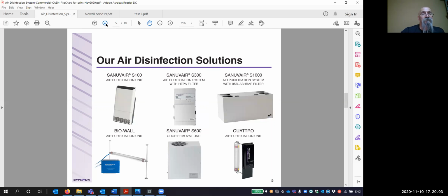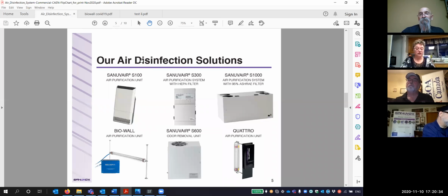Sure. Let's talk about air disinfection. Air disinfection is different than coil cleaning. It's all about time and intensity. With coil cleaning, the coil isn't moving. We have all the time in the world. You just have your UV right there at the coil, nothing's moving, and it's doing its job. With air disinfection, we have pathogens and stuff moving through the air very quickly. At a very low CFM, like 700 CFM, a pathogen or a spore will move over 5.5 feet in 1 second.